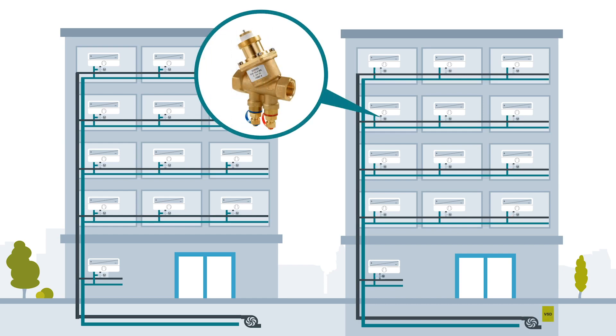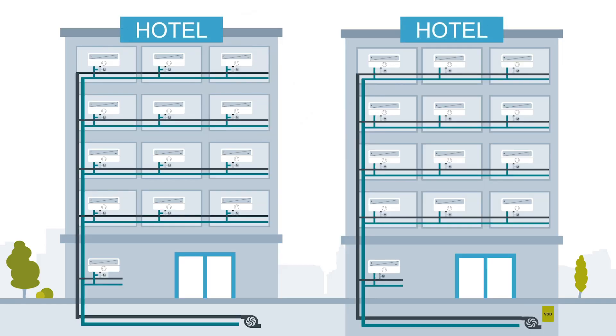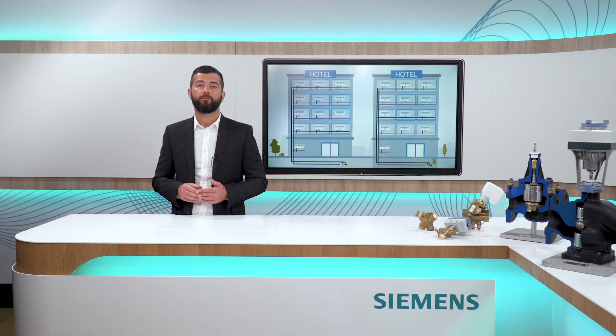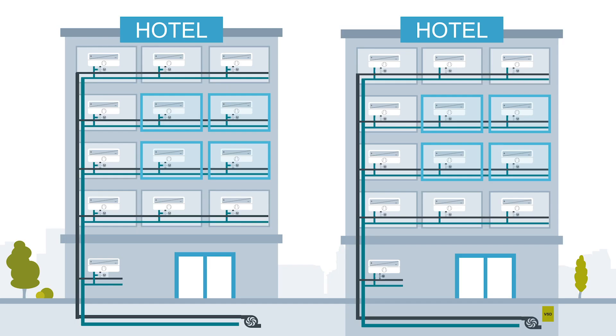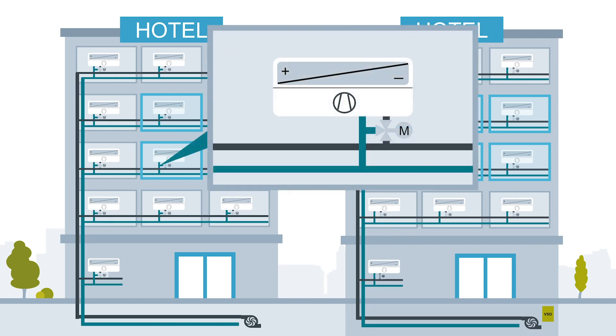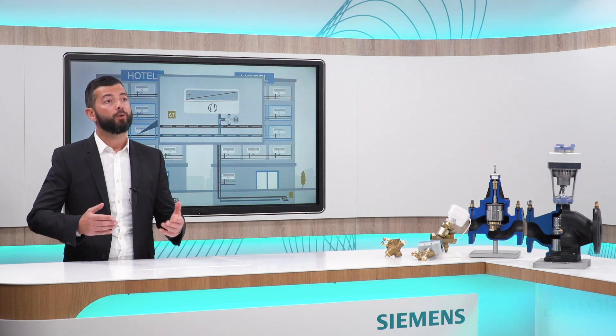Here, Dynamic Balancing Control valves are used for the Fan Coil Units. Let's say our building is a hotel and several rooms are not occupied — the Fan Coil Units can run at minimum temperature set point. In the variant on the left with a constant flow, in a diverting circuit a triple valve simply directs the flow that is not required back into the return pipe. The delta T decreases because the water runs back unused without giving up temperature. That's why energy is wasted.